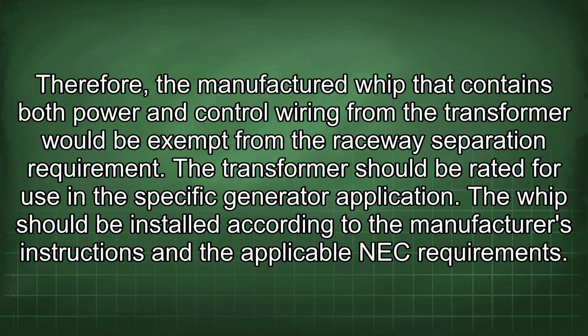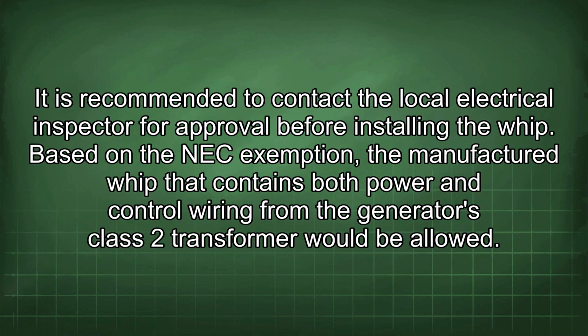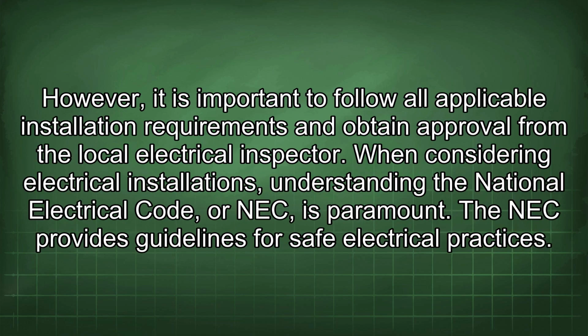separation requirement. The transformer should be rated for use in the specific generator application. The whip should be installed according to the manufacturer's instructions and the applicable NEC requirements. It is recommended to contact the local electrical inspector for approval before installing the whip. Based on the NEC exemption, the manufactured whip that contains both power and control wiring from the generator's Class 2 transformer would be allowed.